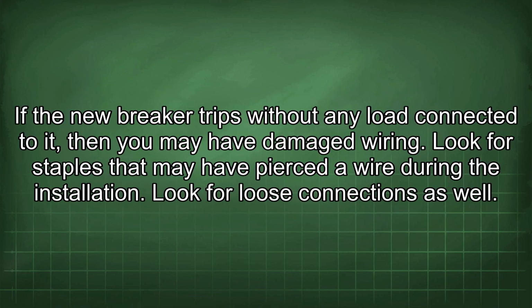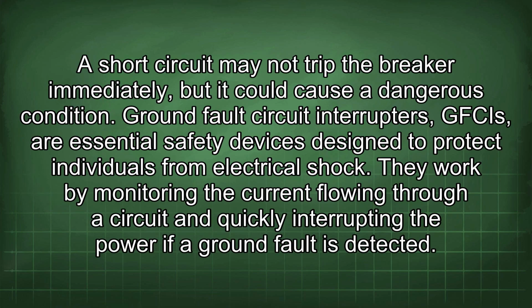If the new breaker trips without any load connected to it, then you may have damaged wiring. Look for staples that may have pierced a wire during the installation. Look for loose connections as well. A short circuit may not trip the breaker immediately, but it could cause a dangerous condition.